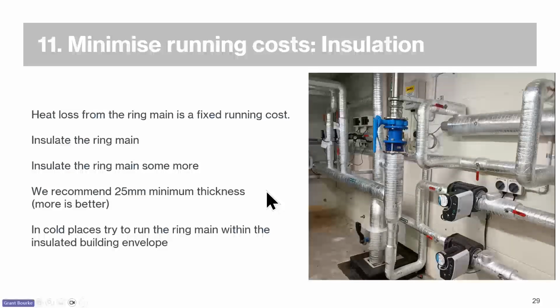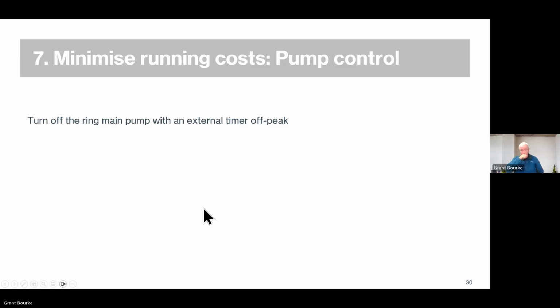In cold places, obviously try to run the ring main inside the building envelope. In Queenstown, don't run it through an uninsulated attic for miles. The second thing you can do to minimize the running costs is control the pump. So turn off the ring main pump with an external timer. We had a customer that reduced their LPG use by 40% by simply adding this onto an existing pump on a little rapid demand duo system that they had on their big house. So a timer: turn it off overnight, turn it off when you're away for the day.